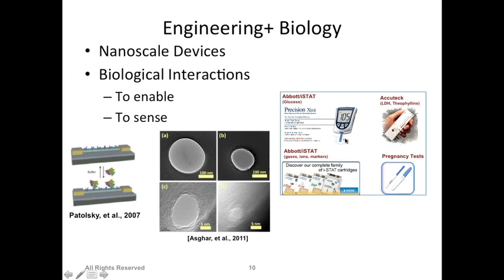And so whenever, again, there are some enzymes which are deposited which react with the glucose and change the conductivity of a solution, and then you actually are reading just the current. You apply some voltage and measure the current. That's what this device does.